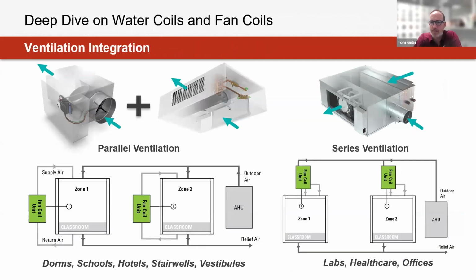Yeah, there's a couple of questions and comments in the chat. Heidi was asking about fan coils serving the same space as the VAV, and you can make a fan coil system behave like a VAV. Yep, even tying in there, but not necessarily simultaneous. Oh, right, you're right. Yeah, so I think this ties into your question there too, Heidi, about the difference between parallel and series ventilation systems. With parallel ventilation systems, you might have a fan coil addressing your sensible capacity requirements for the space, and instead use a VAV for tempering how much ventilation is going to be provided within those systems.